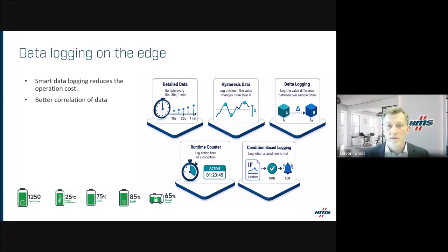Runtime logging basically means you log time on the edge, to see, for example, whether the temperature has been above 27 degrees, and accumulate that. Then you can see the total amount of time the temperature has been above 27 degrees, or running hours, whatever it may be, and get a notification. So you try to implement as much intelligence on the edge as possible, so you don't need to transmit everything.